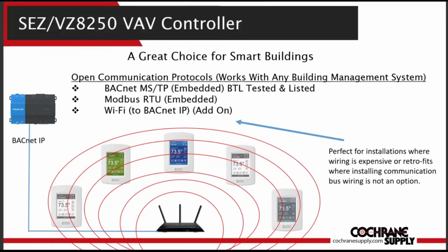Wi-Fi communications allows for network installation in a building that's not suited to traditional daisy chain hardwired network installation. Installations are well suited to locations where the cost of wiring is expensive or where the facility may undergo renovation changes periodically. If they change configuration, there's no need to reroute the communication bus. Additionally, they're great for retrofit situations where the owners would like to have a network, but the construction is not suited to fishing communications wire. Think of locations that are architecturally important, like museums or historical sites, locations that may have asbestos in the walls, or locations that cannot endure extensive downtime, like hotels that can't rent their rooms if there's work being done.